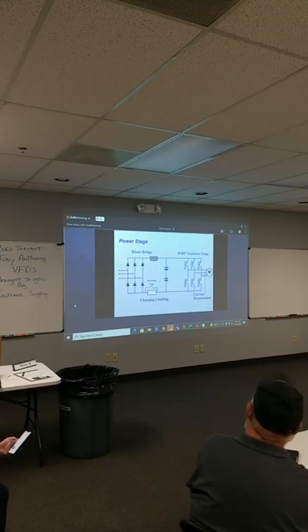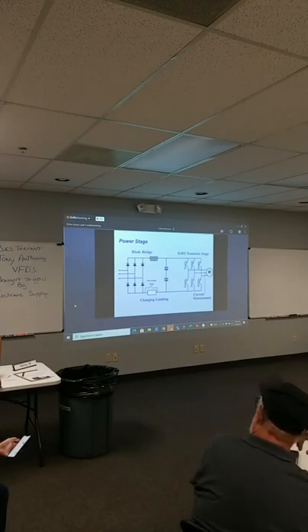And as was said in the video, you see that pre-charge relay, and there's a resistor in there. That is in there so that when you first apply voltage and power to a drive, the DC bus capacitors, which are an instantaneous short, don't draw a huge current. The resistor limits that inrush current until those capacitors build up. If you've ever been in front of a big drive, you hear that big clunk about a second or so after you put power on it. That is the contactor around the pre-charge resistor kicking in to take the resistor out of the circuit because the capacitors are now charged up.